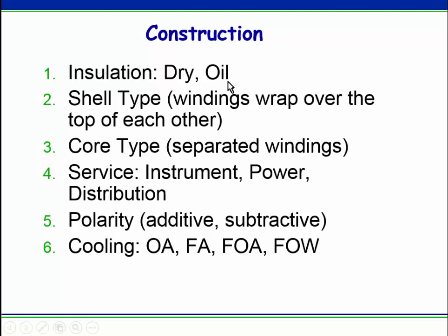Typically power transformers are oil filled. We have oil for insulation. There are other types of insulation in there too, but the oil provides insulation and cooling. There are dry type transformers, but those are typically indoor transformers. The oil transformers are usually outside because you have extra fire and explosion concerns with oil. But with oil, you get a smaller package, right? You can get more kVA in a smaller box if you cool it and insulate it with oil as opposed to air. All right, we'll look at shell type and core type.